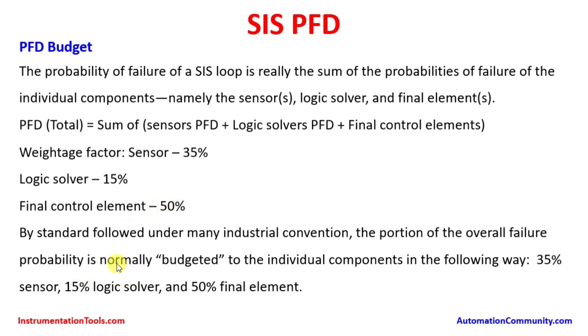By the standard followed under many industrial conventions, the portion of the overall failure probability is normally budgeted to the individual components as follows: 35 percent for the sensor, 15 percent for the logic solver, and 50 percent for the final element. This distribution differs because of the wear and tear of the components and the impact on the probability of failure on demand. This is a general industrial standard used across industries.